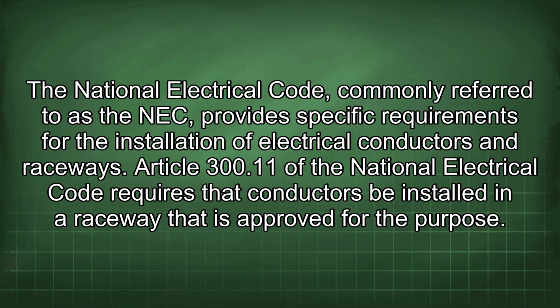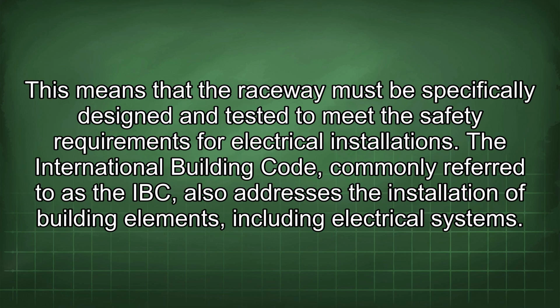The National Electrical Code, commonly referred to as the NEC, provides specific requirements for the installation of electrical conductors and raceways. Article 300.11 of the National Electrical Code requires that conductors be installed in a raceway that is approved for the purpose. This means that the raceway must be specifically designed and tested to meet the safety requirements for electrical installations.